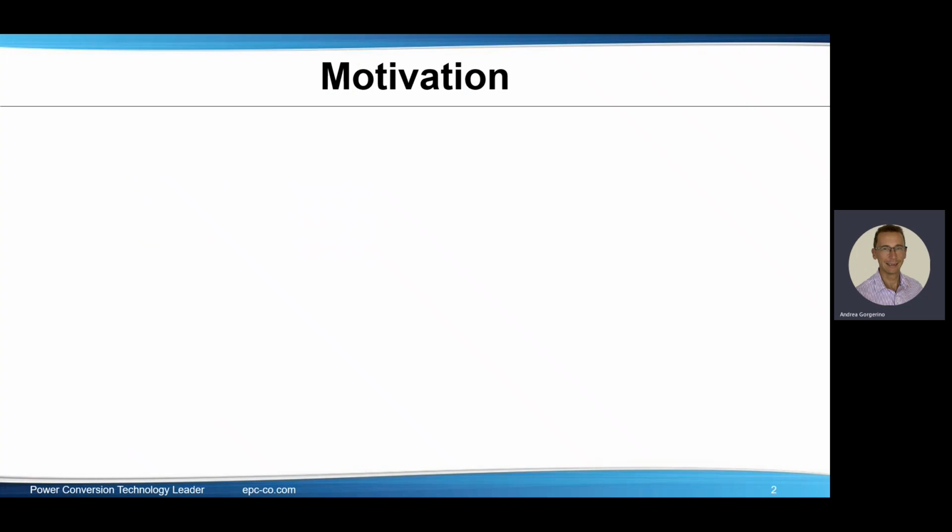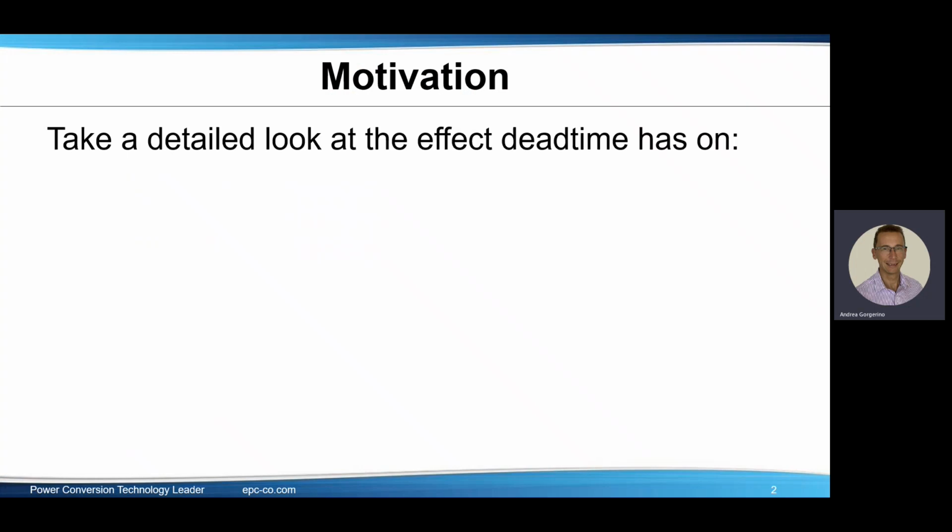The topic of our discussion today is understanding the impact of dead time in motor drive application. So let's start with the motivation. We want to take a detailed look at the effect of dead time on inverter losses, and in particular switching losses, which are dominant in inverter applications. However, they're often not very well understood, and in particular, the dead time losses, which play an important role in the overall switching losses. But we will also take a look at the motor behavior and how dead time affects the system level behavior of motor drives.